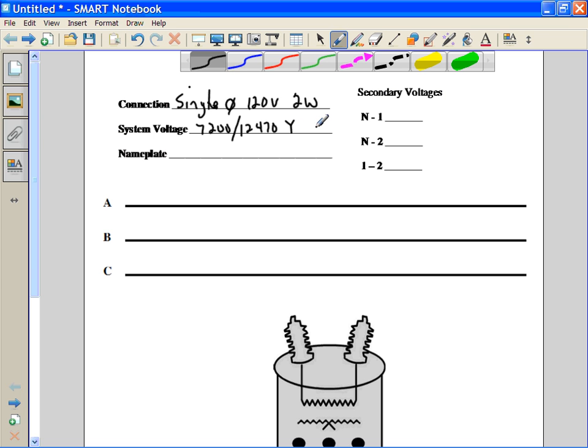So our nameplate rating on the transformer, in other words, if we go out to find this transformer in the transformer yard, and we're looking at nameplates to get the correct transformer for this application, is going to have 7200/12470 for the primary voltage rating, and in this case it's going to be a 120/240 volt secondary rating. And the reason it's both 120 and 240 is because the transformer we're using can either be wired internally on the secondary coils to put out 120 volts or 240 volts, even though in this instance we're going to just connect it as a 120 volt service.